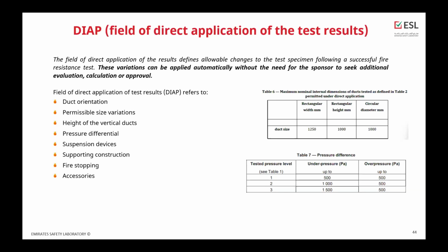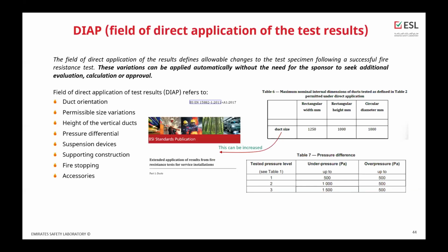So what does this field of application refer to? It of course refers to the duct orientation, the size, the height of vertical ducts, the pressure differential, suspension devices, supporting construction as I described before, fire stopping, and accessories. The size of the duct can be increased by using the EXAP standard 15882 part 1. This is only for ventilation fire-rated ducts.